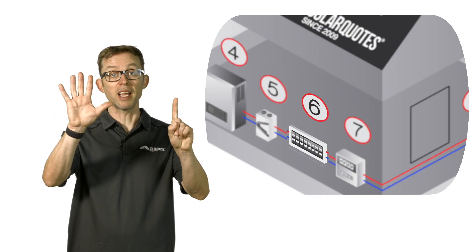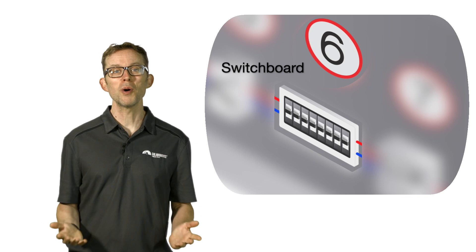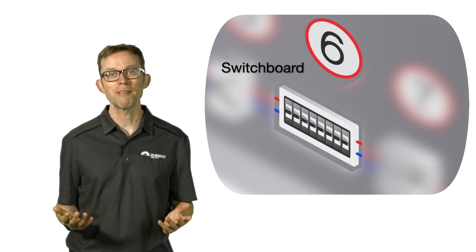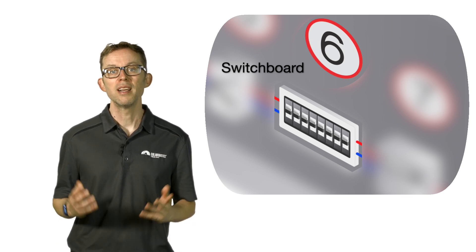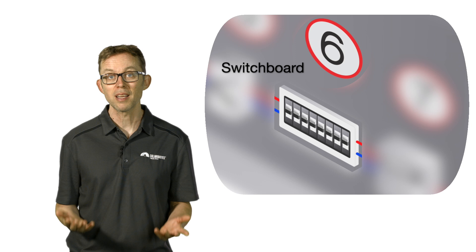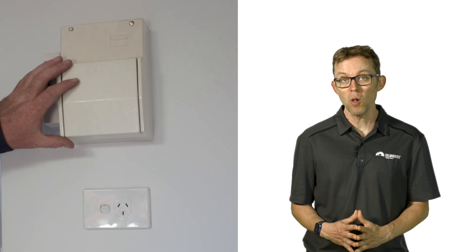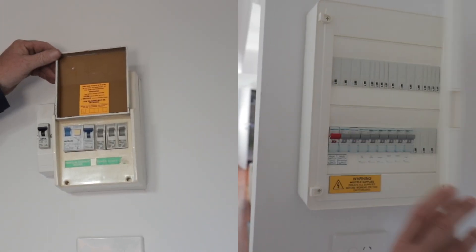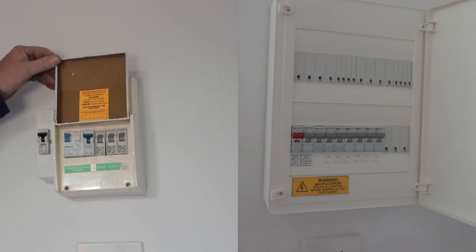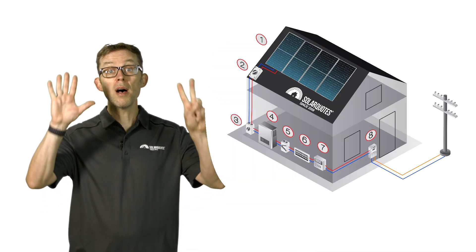Number six: the switchboard. The switchboard contains the breakers for every circuit in the house. It is where the grid and your solar inverter connects into your home. Your installer will need to add a circuit breaker for the inverter in the switchboard. Ideally, they'll add a consumption monitor as well. If your switchboard is small or old, installing a solar power system may also require a new switchboard. This adds approximately twelve hundred dollars or more in costs.